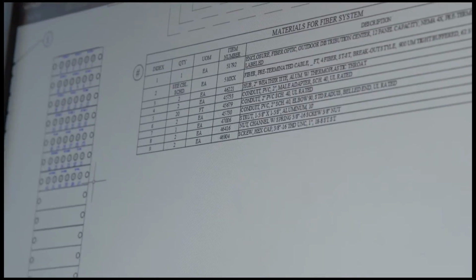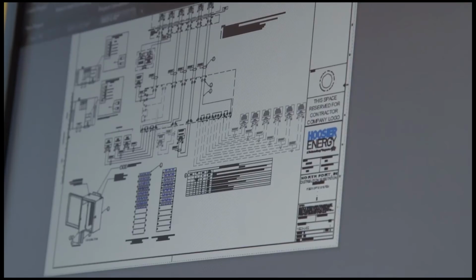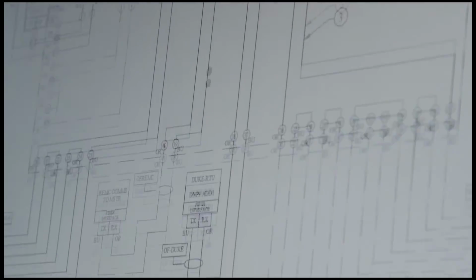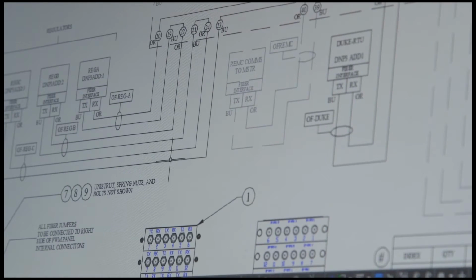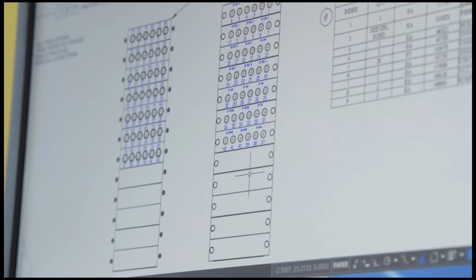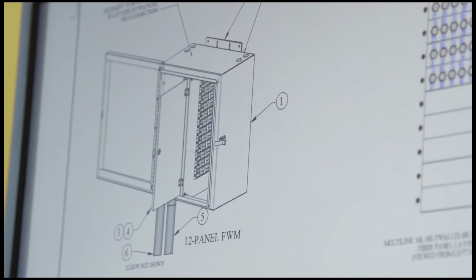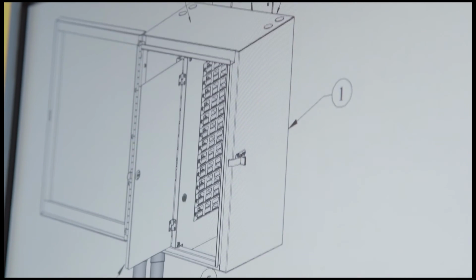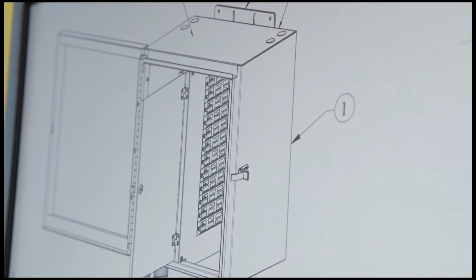So we decided to investigate different manufacturers that provide pre-terminated cables, made in a clean environment and tested before they leave the factory, as well as options to have the fiber optic termination panels at the stations pre-made and labeled, so that our technicians just need to go to the site, pull the cable, and plug them in.